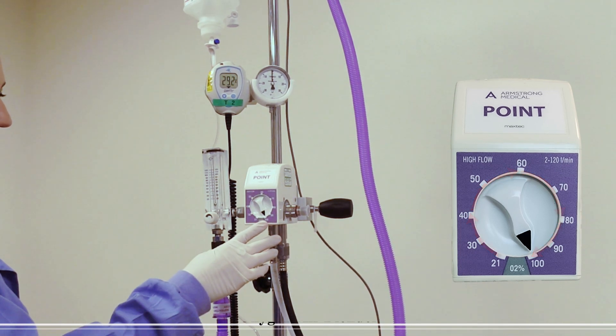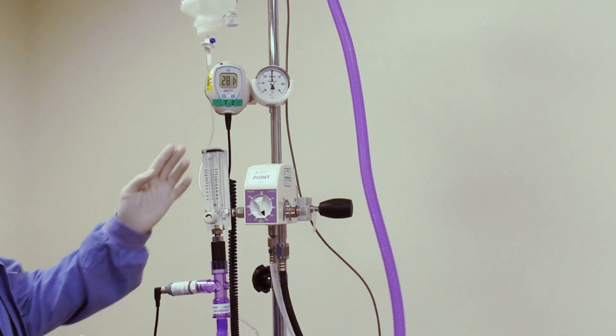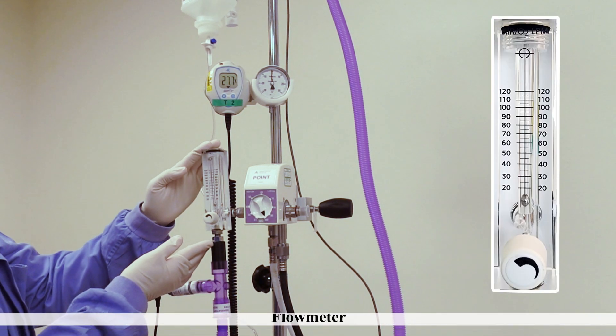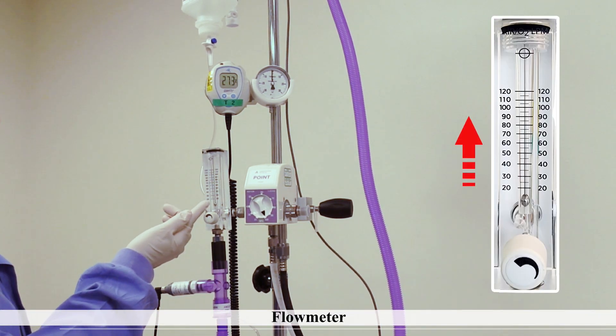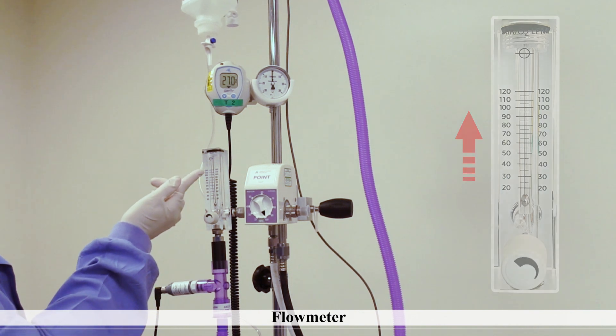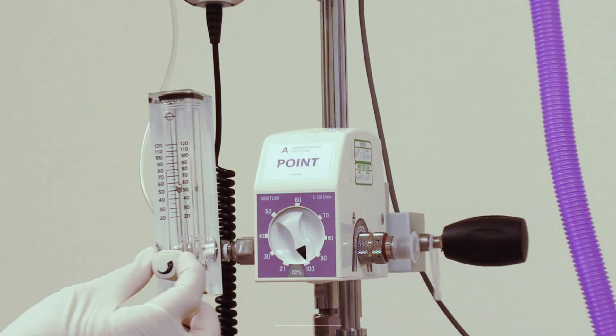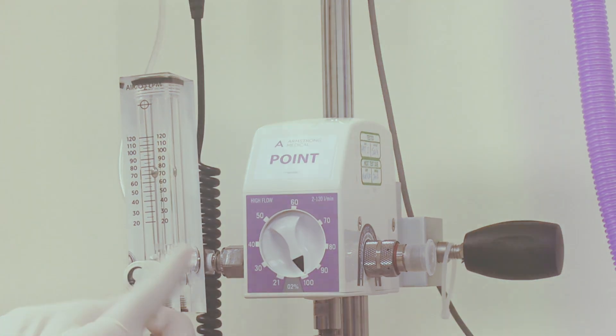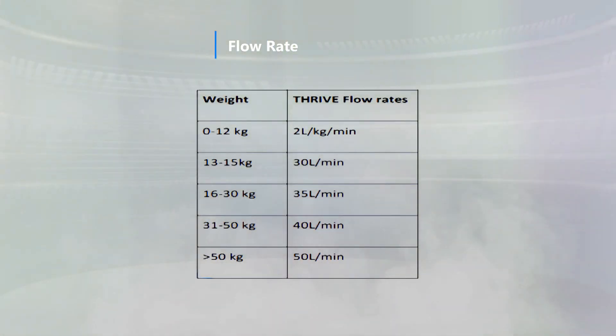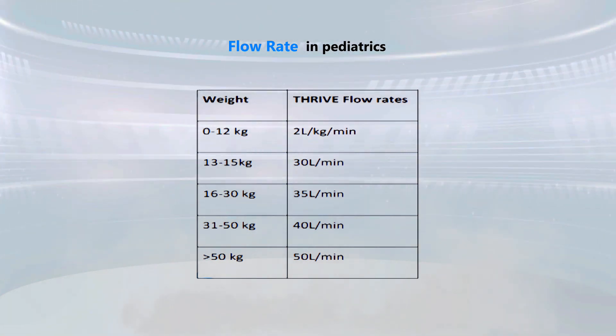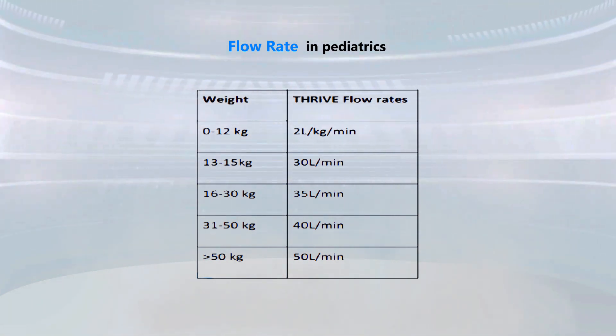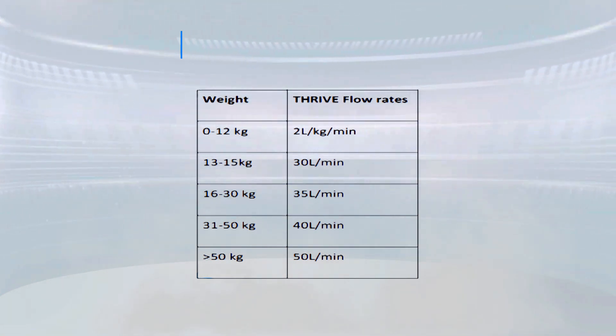Next is the flow meter, capable of delivering up to 120 liters per minute. For BiPAP mask ventilation, a flow rate between 80 to 120 liters per minute is utilized. For high flow nasal oxygen therapy, the recommended flow rate for children is provided in the table displayed on the screen, while for adults it is advisable to maintain a flow rate within the range of 50 to 80 liters per minute.